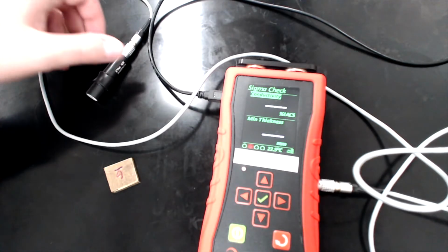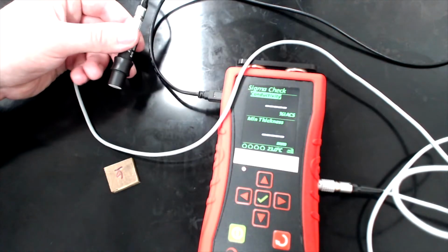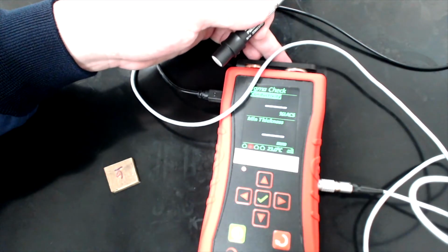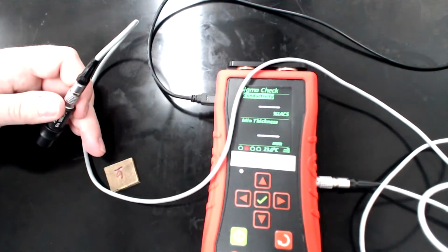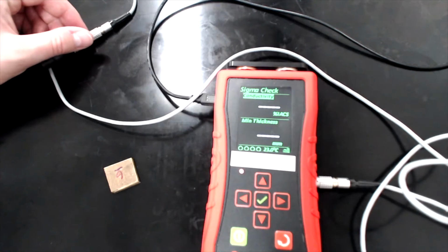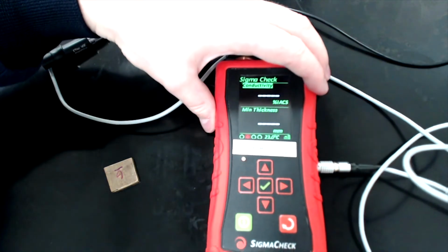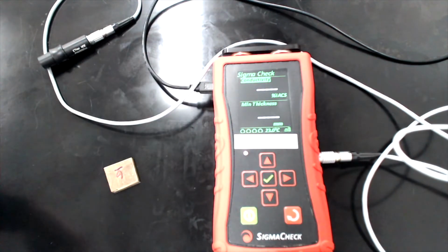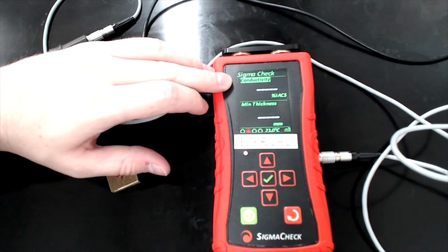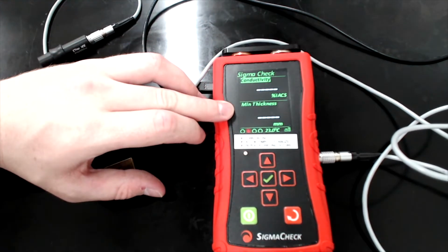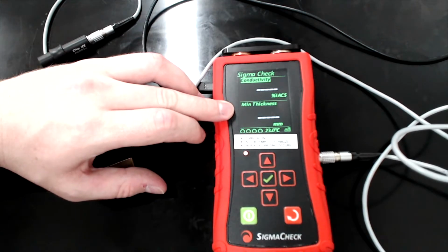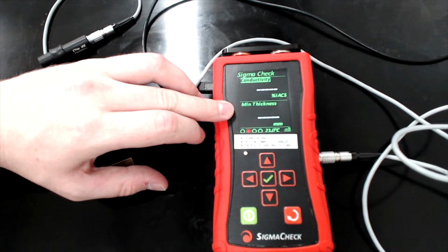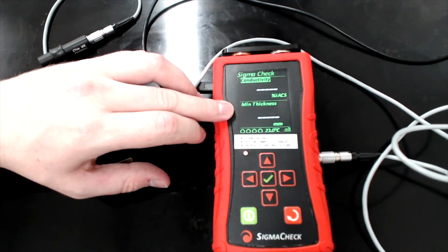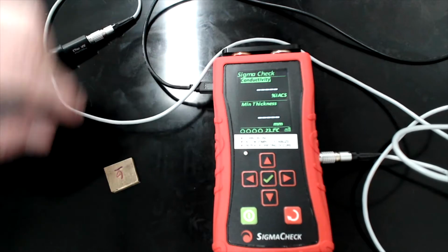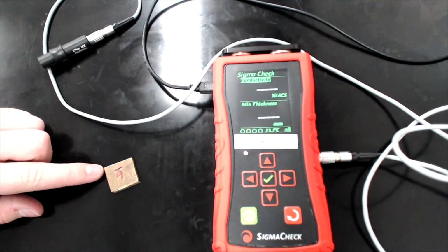Okay, but that's all you have to do to run tests, is you basically place this probe onto the surface of something. We have the standards up here on top of the machine, and then we can also test this. So once we are satisfied with the calibration and with it not drifting, we are ready to test. On this home screen, like I mentioned before, it has conductivity. It has, in this case, listed minimum thickness. So this is a function of frequency and the probe that we have. And it tells us, based on the conductivity of the sample, what our minimum thickness has to be for the test sample to ensure that we have a valid test.